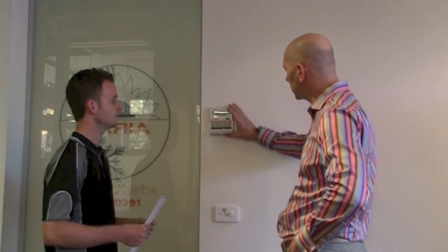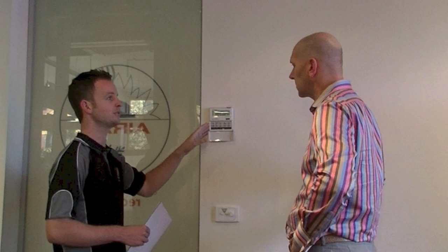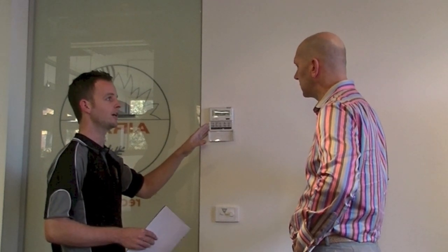When I left work the other day, I noticed that the system was still running. Is it a good time around daylight savings to think about resetting your system, or should we have you do that? It's important and imperative that you check your time clock every single time that you're here. Power spikes and power outages can throw out time clocks, so we just need to ensure that the time is correct and your on and off times are correct. That stops unnecessary run-on and stops starting too early in the morning, just consuming excess energy for you.